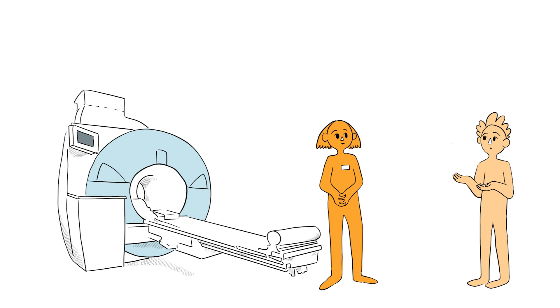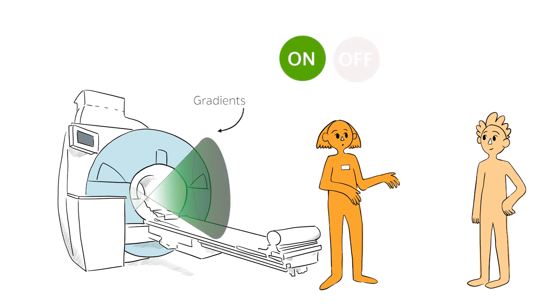Why? Will it be noisy? Yes. It's noisy because we use additional smaller magnetic fields during the scan. These are called field gradients. We switch them on and off to work out where in the brain the signal is coming from. Switching the gradients on and off causes banging sounds that you hear when you're in the scanner. These can be very loud, so we give everyone ear protection. Here is an example of the types of sounds you may hear in the scanner.